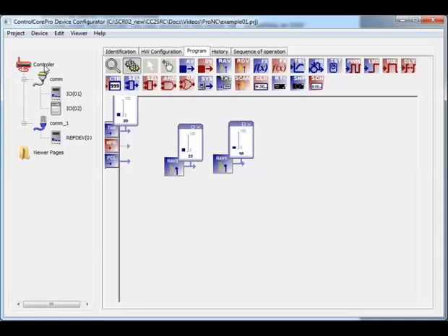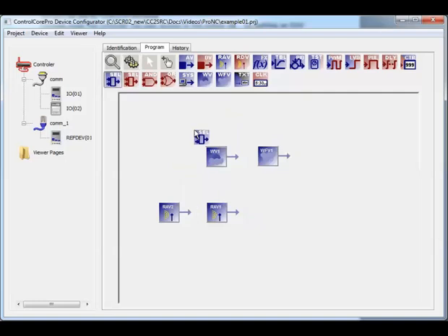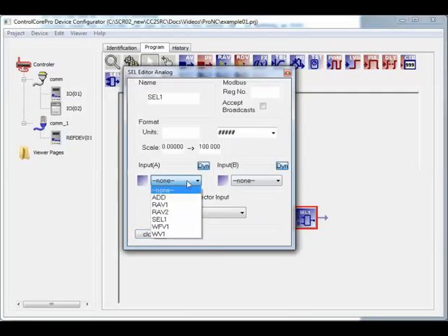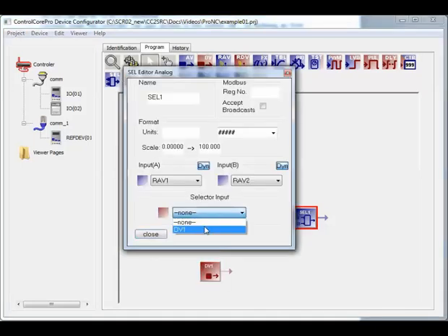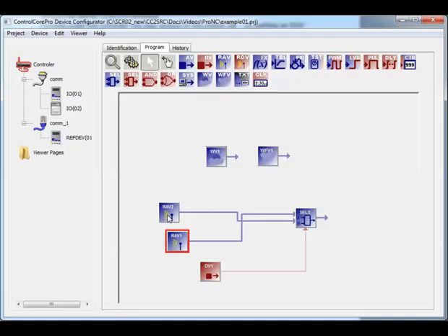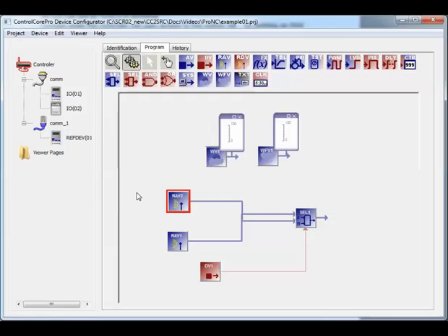In this case, the controller is actually a PC running NC server, so it has nearly limitless amounts of space for its supervisory program. The iCore device will not have limitless space, but it will have a lot more space than any device. We are talking megabytes, not kilobytes. So you will have 1,000 times more space for the controller's program. If one of your programs inside a device is very tight on space, you might consider letting the controller's supervisory program handle some of the logic and use an RAV to get the resulting value.